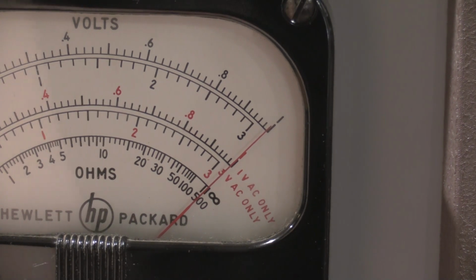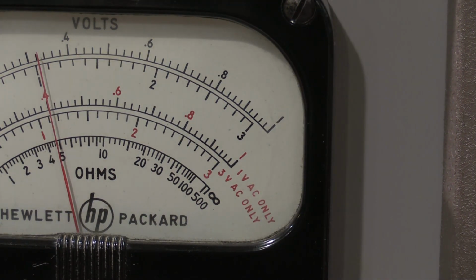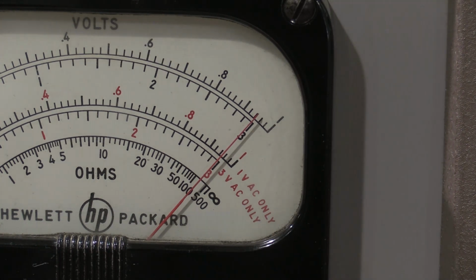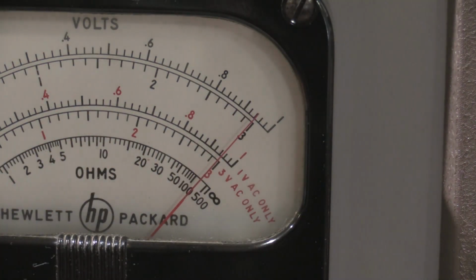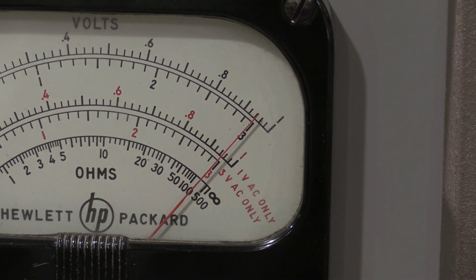Let's check 30. And then bounce this up to 30. But as you can tell from the shadow being off, the camera's not straight on, but I'm also not at 30 volts either. That's a good 30 volts on the 7510. And I will freely admit, it is way excessive to be comparing this HP meter to a 7.5 digit modern meter. However, the HP is performing very well.